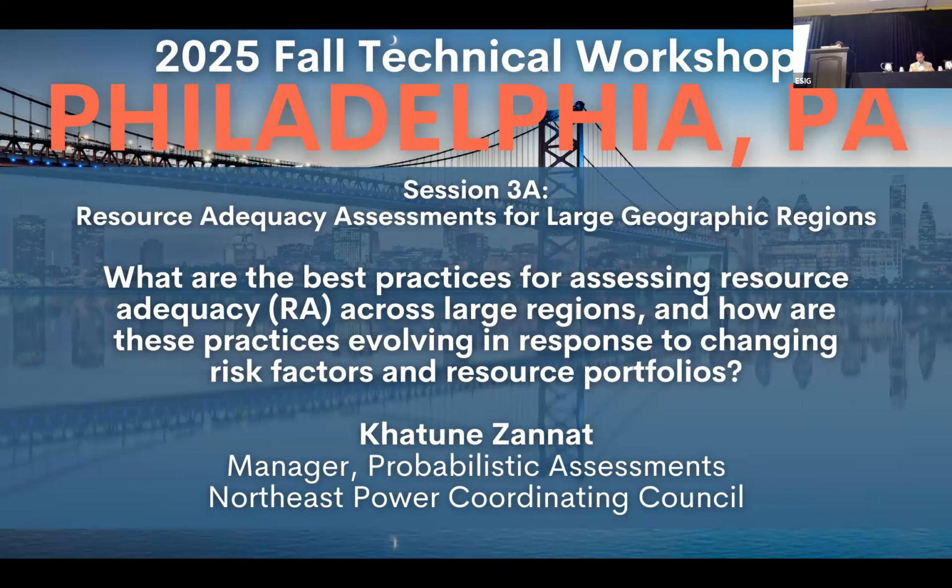This year, we included a scenario-based analysis, which is tailored to the distinct characteristics of each of our 5 NPCC areas. In this scenario, we considered regional specific factors that influence reliability. I'll give one example of what we considered. Hydro-Quebec, which is the Quebec system, is heavily reliant on hydroelectric generation. So as part of our scenario, we accounted for a potential drought condition that could impact resource output.